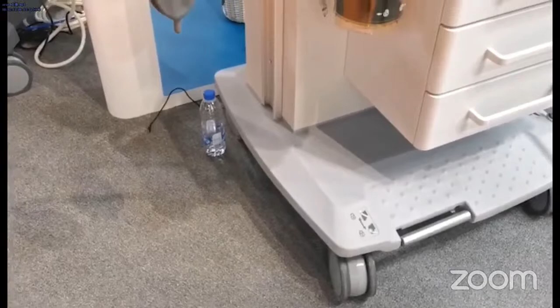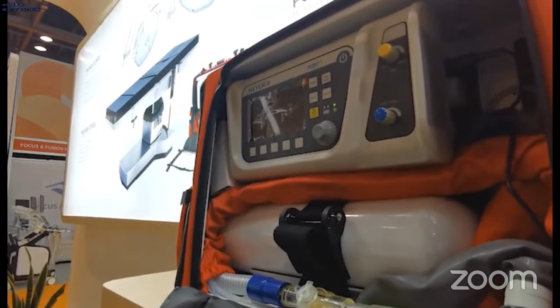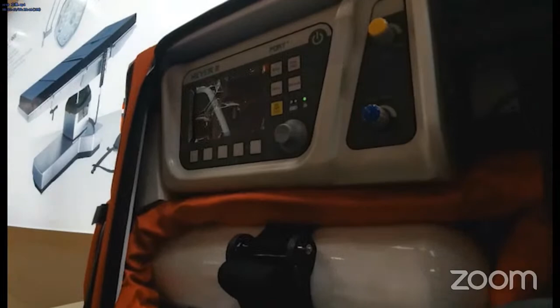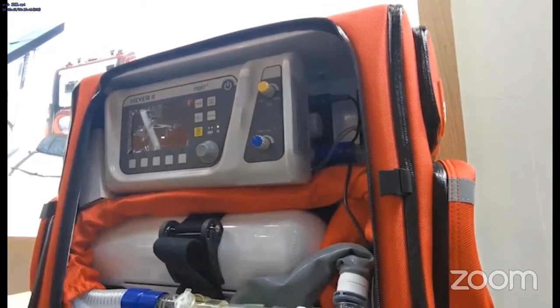Our Port Plus transport ventilator. The weight of the main unit is 3 kilograms, and the weight of the whole unit with the accessories is 8 kg. So as we see, it's very light and easy to move for transport or for emergency cases. The size of the screen is a 5-inch touch screen with the navigator, and the tidal volume for this machine goes from 0 to 2000. The oxygen concentration goes from 40 to 100, and it has various ventilation modes. Also, it has a flow trigger and pressure trigger. So the machine is compact, easy, and very simple in design.